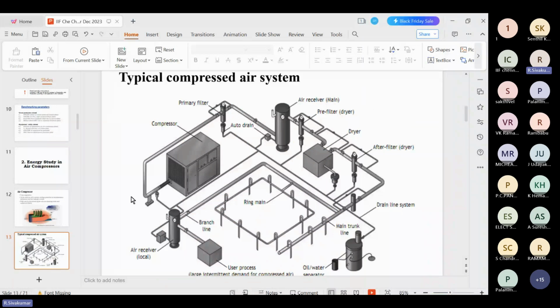This is the typical compressed air system layout. Nowadays it is followed with a complete ring main system. The generation compressor is there, then the primary filter. After the primary filter there is the air receiver. After the receiver, a pre-filter is there before the dryer, and the air dryer removes all the moisture. Then the dry air goes to the outlet area. There are so many filter elements. In the distribution area, the ring main system reduces pressure drop and pressure losses, so compressor efficiency increases and compressor energy consumption is reduced. This is the complete ring main system structure.